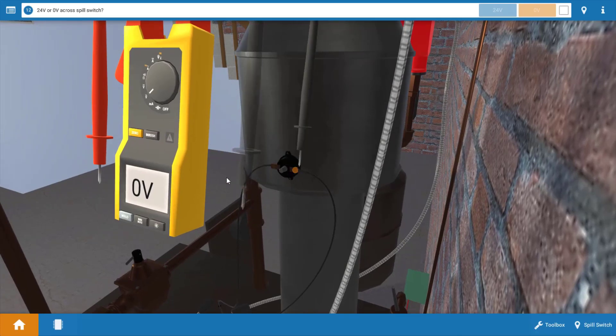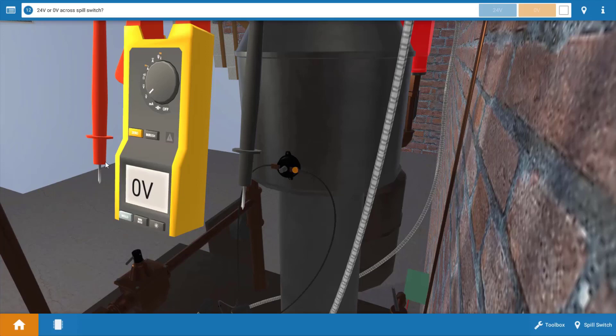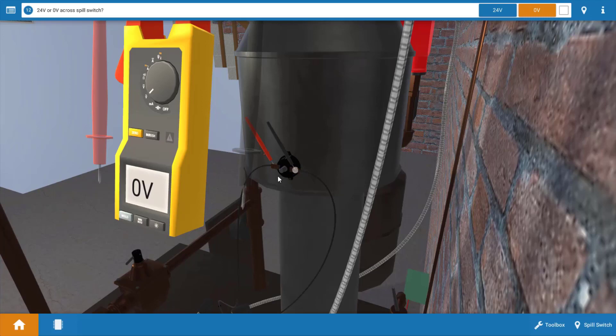And as we do that, we can see on the meter we have zero volts. Again, this verifies the spill switch is closed, so this isn't our culprit.